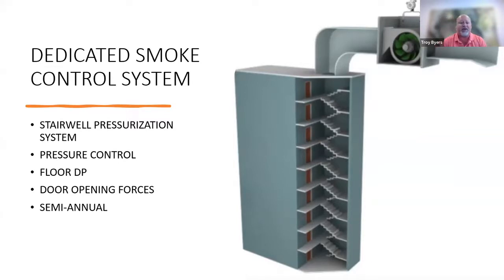door opening, so that we don't have excessive opening forces on the doors. So our differential pressure across the boundary at each doorway is limited to a range of 0.15 inches to 0.35 inches of water gauge. It's a little different for us. We're 0.1 to 0.3 here in Oregon.